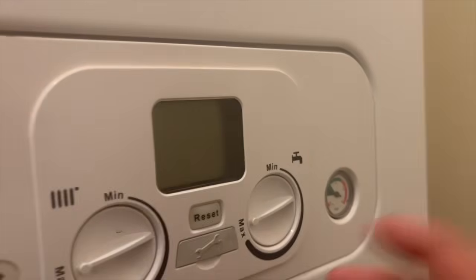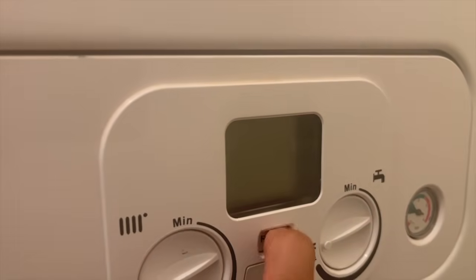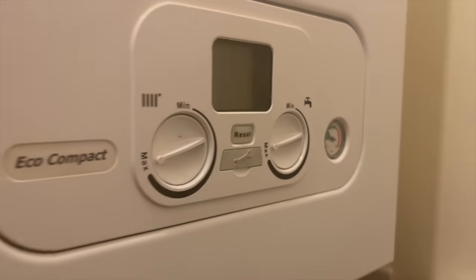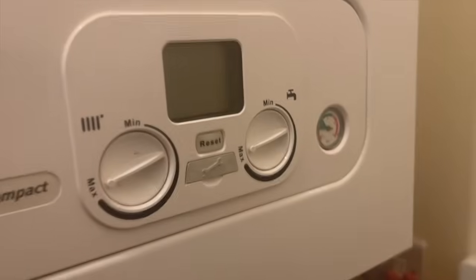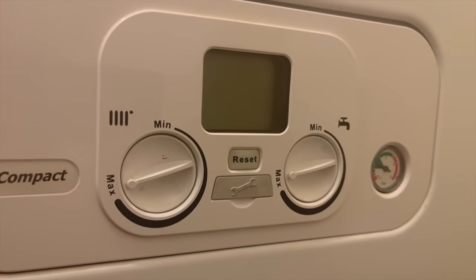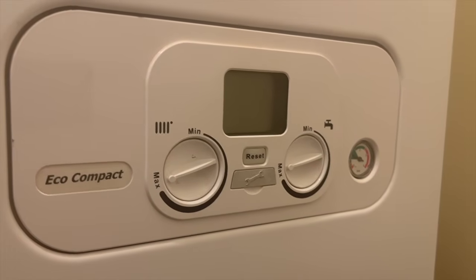For this first job we've got a Main Eco Compact that seems completely dead, but if you listen closely you can still hear it running. When I switch it off you hear it go silent, and when I switch it back on you can hear it starting to run. I believe that the screen on this boiler is dead, but to change the screen you have to change the PCB, so this boiler we're changing over the PCB.